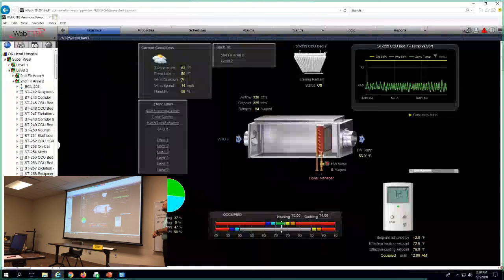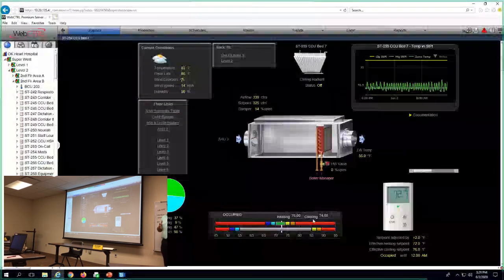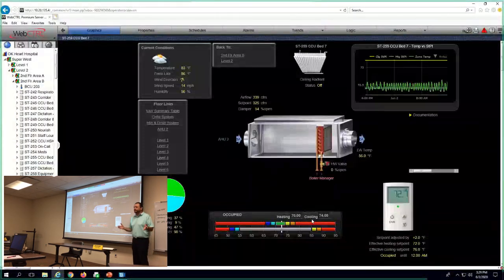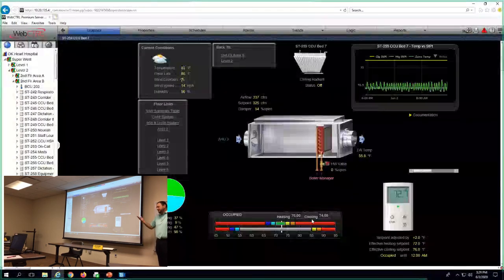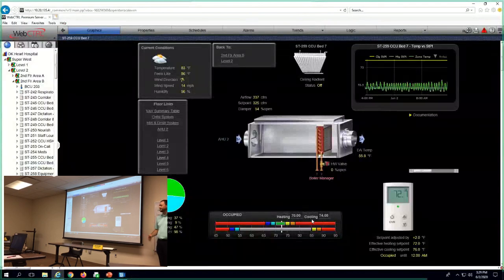Which one is it? So 4 degrees is not what the sequence says; it needs to be 2 degrees. But there's a lot of zones in the building that are set to a 4-degree deadband. In an office building, schools, places like that, it depends on the time of year, but 74 to 70, most people don't have a problem with. Some probably feel the difference, but we can help you guys change all those to whatever.